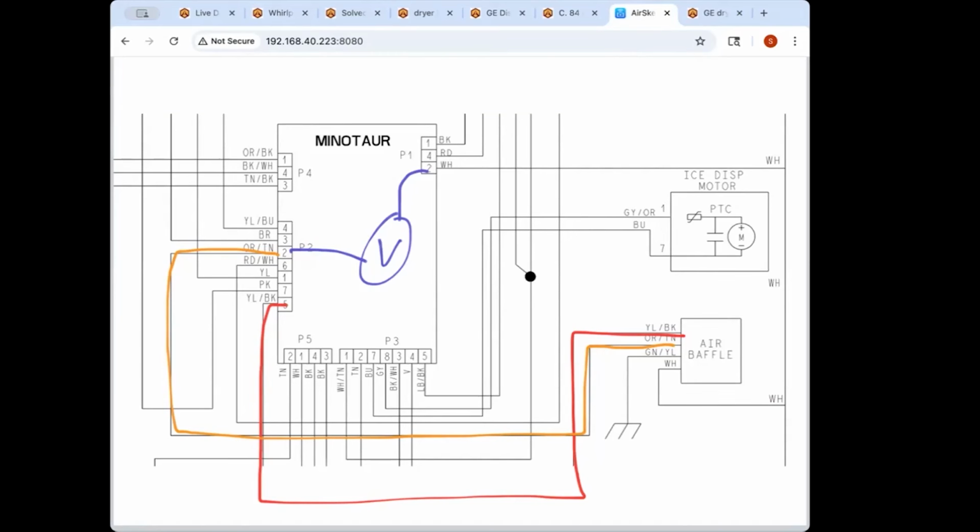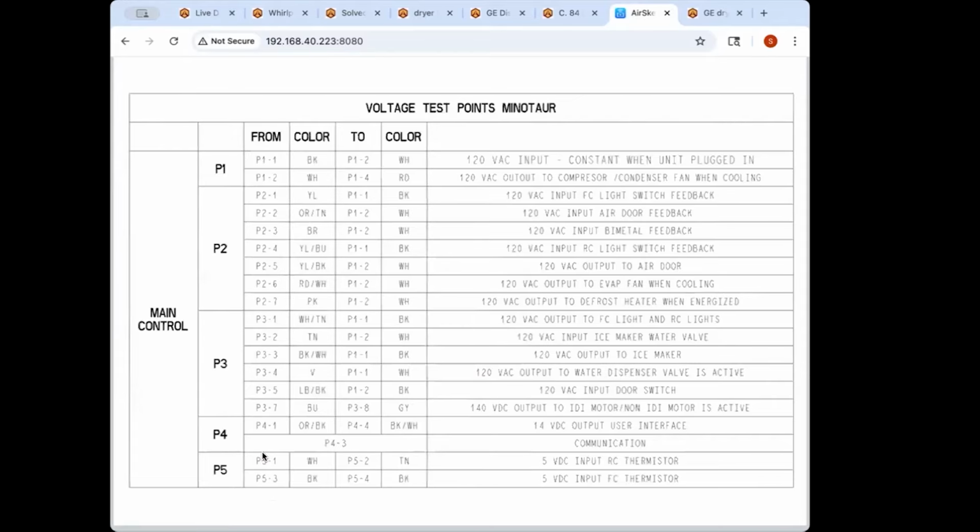And I know you guys probably said this and I probably missed it. What would be the frequency if we're doing the test with our meter there? What would be the frequency, or how many seconds in between would we see the voltage reading change? If it's in spec, it takes about 10 seconds. Every time it reaches the end, it completes the state change of the damper.